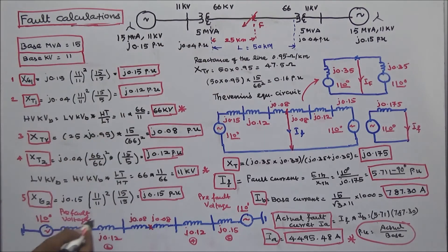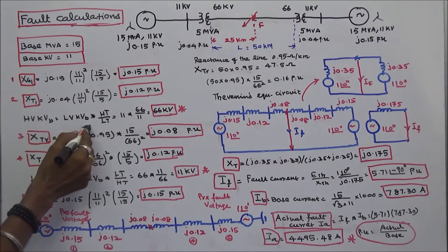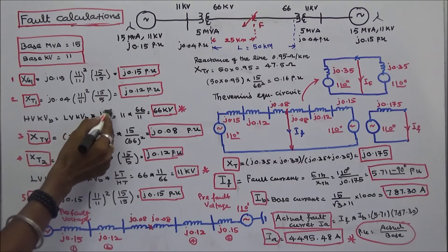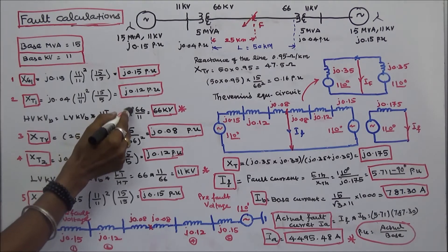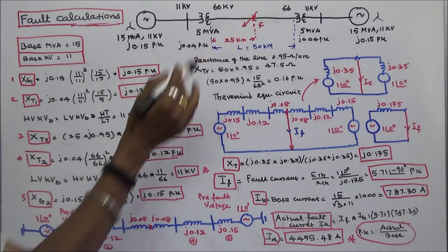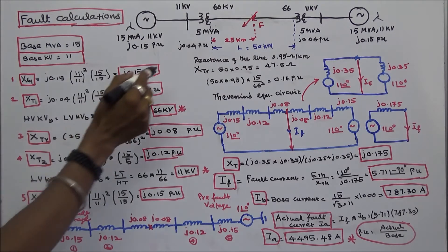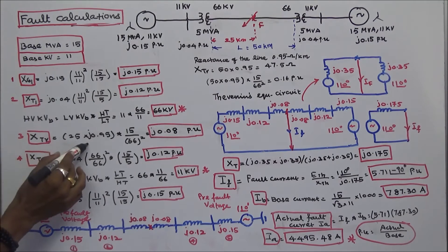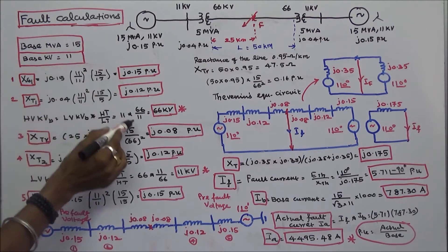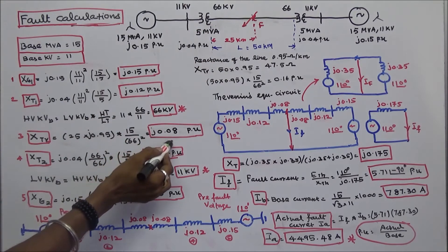Next, we calculate the high-voltage KV base. High-voltage KV base equals low-voltage KV base (11) × (HT/LT), where HT is 66 and LT is 11. So 11 × (66/11) equals 66 KV — that is the transmission voltage. For the transmission line, the reactance up to 25 km is: 25 × J.95 × 15 ÷ 66² = J.08 per unit.